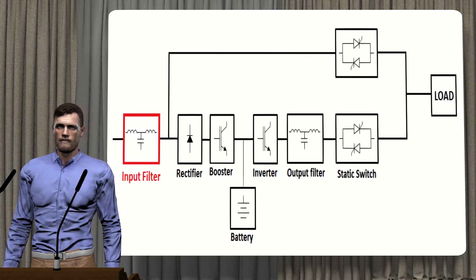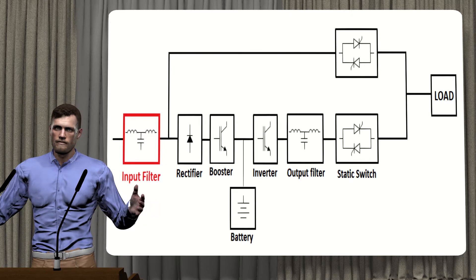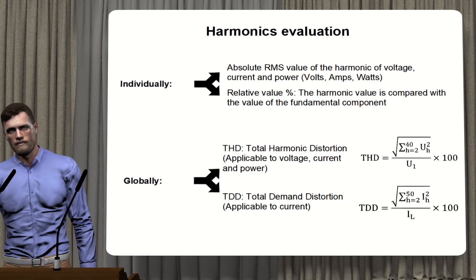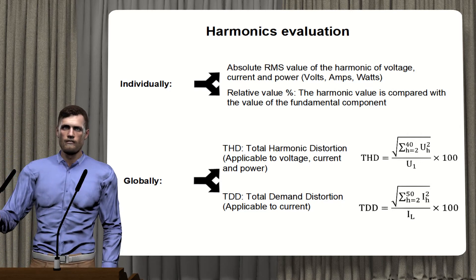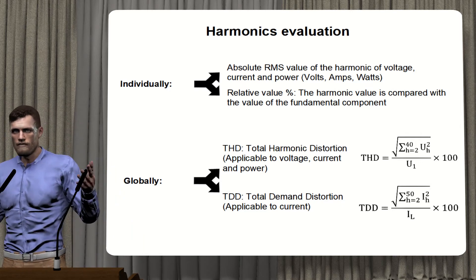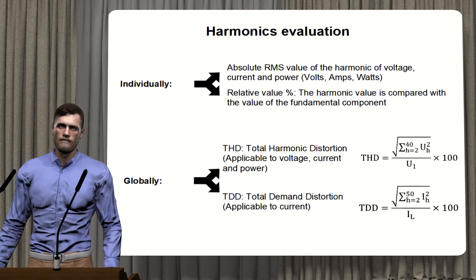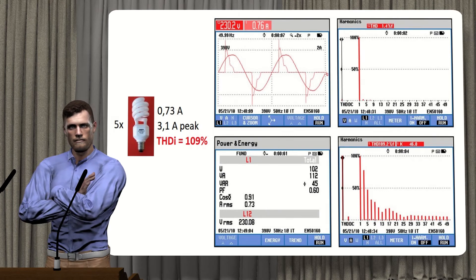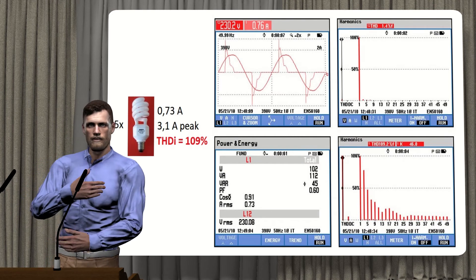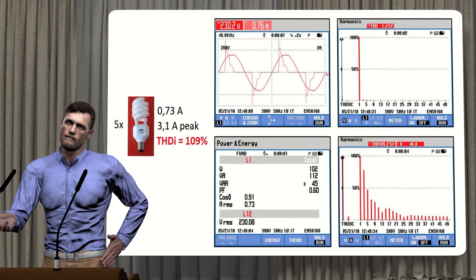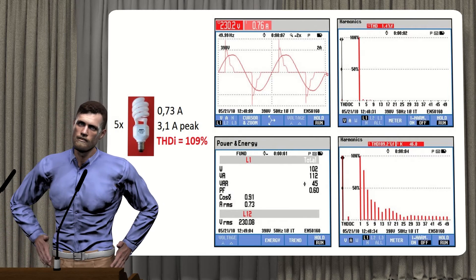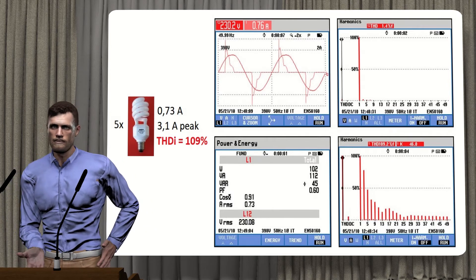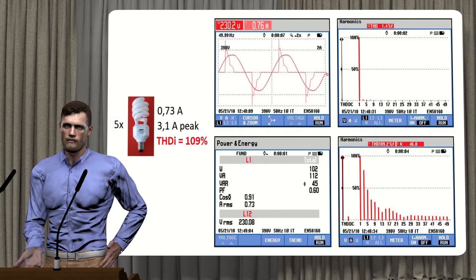Although THD is a good tool to control voltage distortion, current THD does not always give us a clear vision of the impact that harmonics have on the installation. For example, let's consider a current low consumption light bulb that we can find in a supermarket. As we can see in the image, the current THD can be higher than 100%. A 100% current distortion is actually a very high value. However, in this case the impact that the current harmonics generated by the bulb may have on the installation will be minimal, since the current consumed by a single bulb is small compared to the capacity of the installation cables.